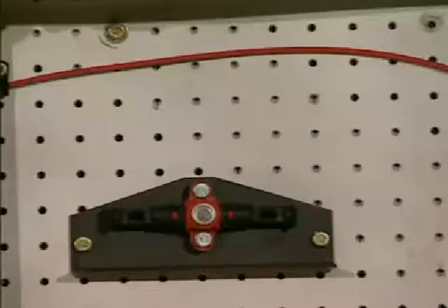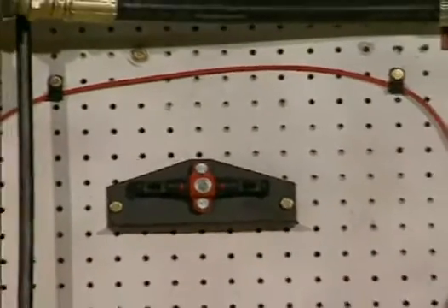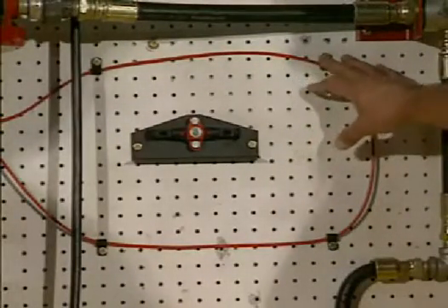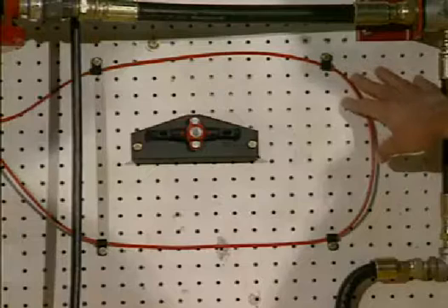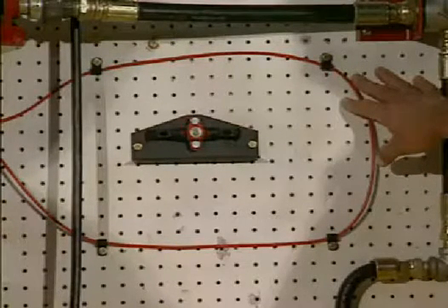Okay. This is a thermal detector, which is this device right here in the middle. You're going to have the same problem with this detector as you are with that. If you get a coat of anything on there, it's going to change the rating on that particular unit, whether it's a detector or a detection wire. If you get a coat of mud on it, you're automatically going to change the rating. It's no longer going to be the same rating because of that mud, paint, or anything on those.